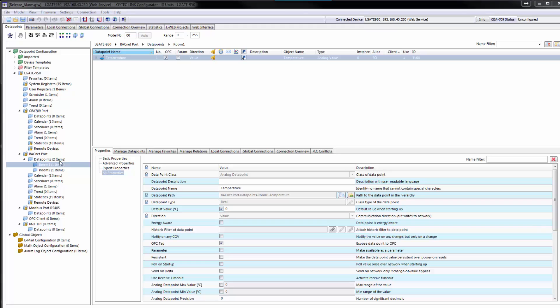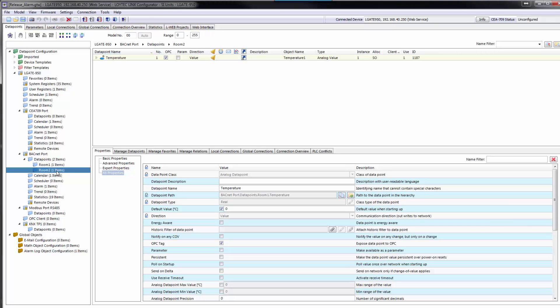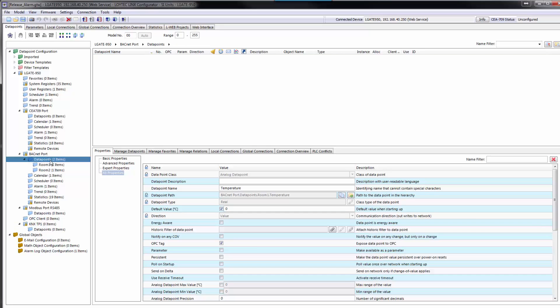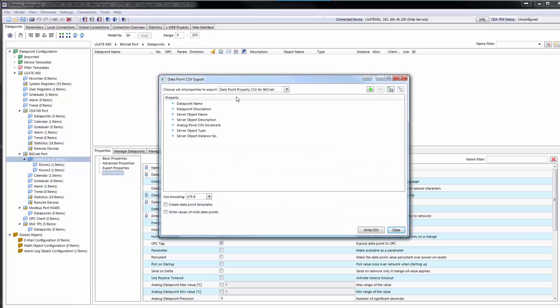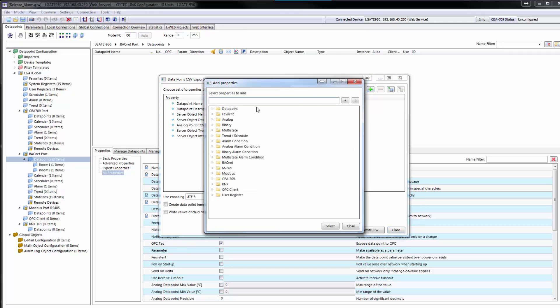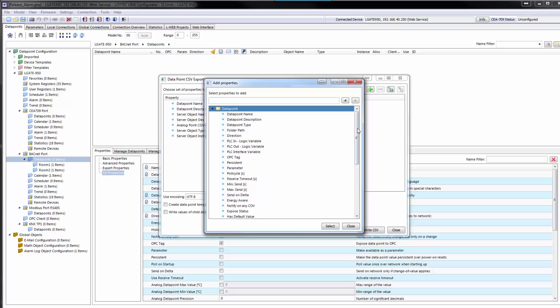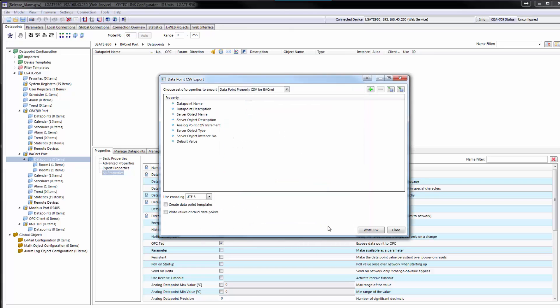The entire CSV import/export engine of the configurator has been revisited. Special export options with fixed columns for CEA-709, Modbus, and other technologies have been replaced by a general CSV engine that is able to configure columns for any set of data point properties. Default property sets have been added, which can be modified by the user and saved for later use in a comfortable export editor.